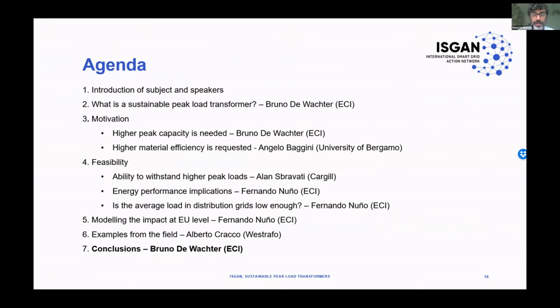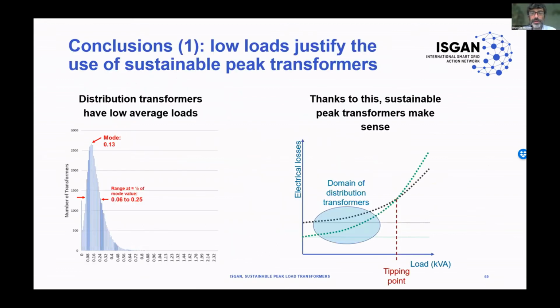Thank you, Alberto. So after this, we will conclude with a short wrap-up of our entire presentation. The average loads in distribution grids are low. Measurement campaigns have proven that they are even lower than we thought before. And this means that the load in a classical distribution grid is within the field where it makes sense to use a sustainable peak load transformer, namely the field where the no load losses are dominant over the load losses.